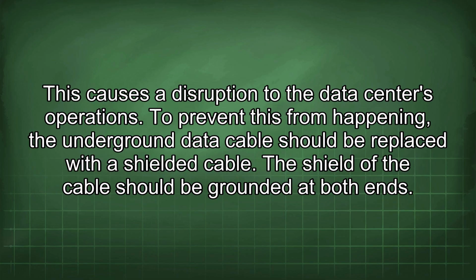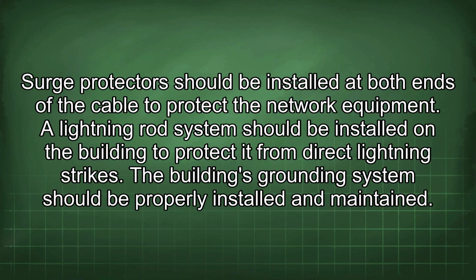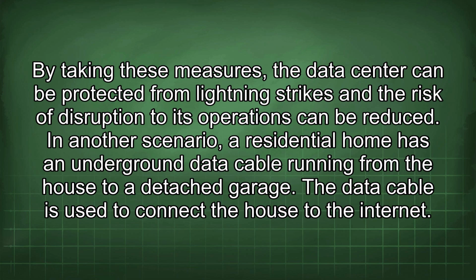To prevent this from happening, the underground data cable should be replaced with a shielded cable. The shield of the cable should be grounded at both ends. Surge protectors should be installed at both ends of the cable to protect the network equipment. A lightning rod system should be installed on the building to protect it from direct lightning strikes. The building's grounding system should be properly installed and maintained. By taking these measures, the data center can be protected from lightning strikes and the risk of disruption to its operations can be reduced.